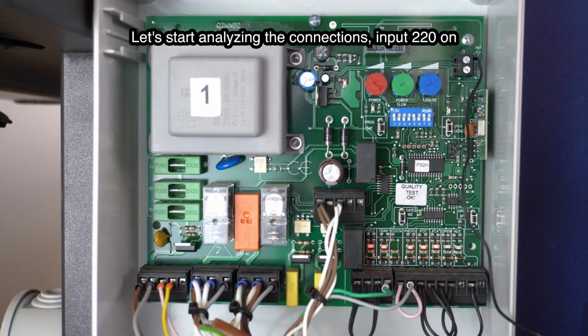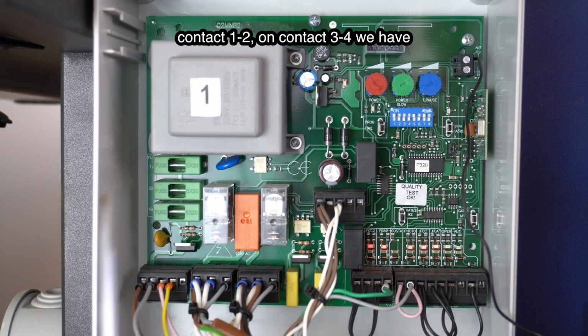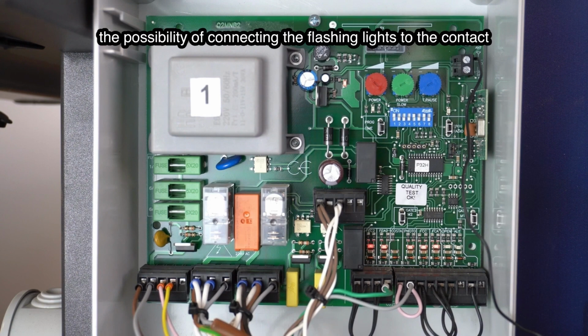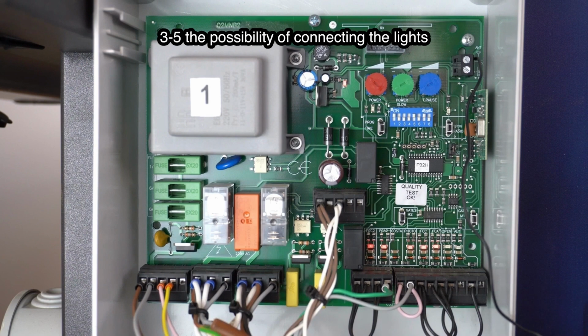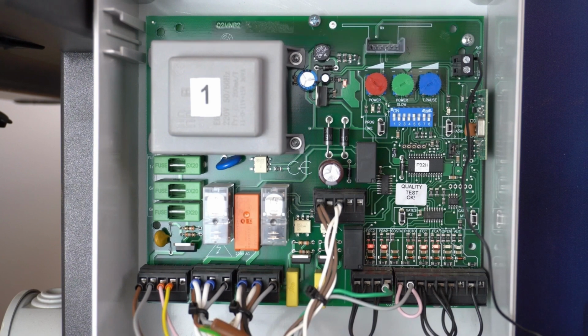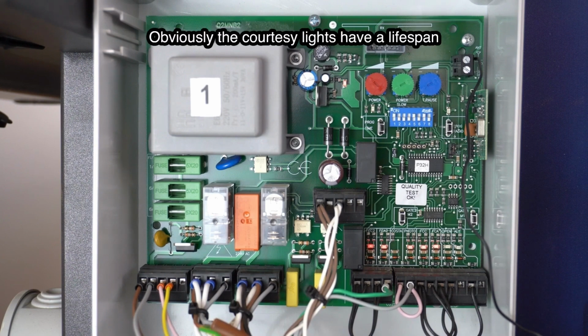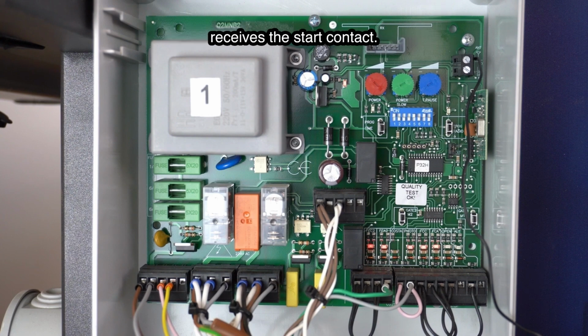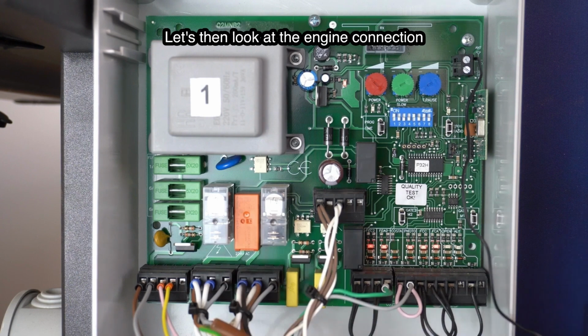Let's start analyzing the connections. 220 volts input on contacts 1 to 2. On contact 3 to 4 we have the possibility of connecting the flashing light, and on contact 3-5 the possibility of connecting courtesy lights. The courtesy lights last for 180 seconds. It receives the start contact.